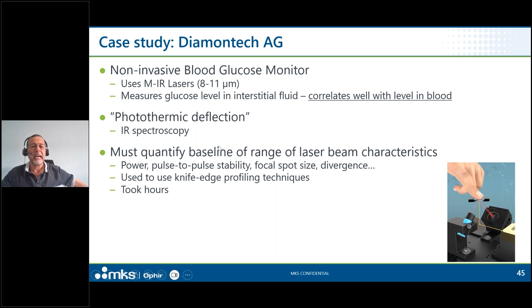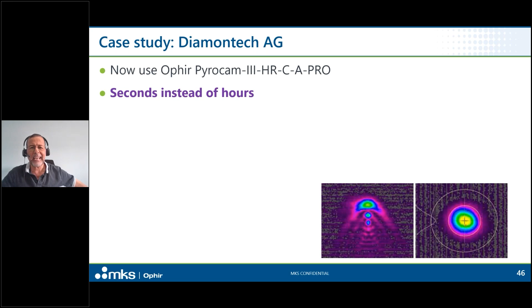So for the beam profiling aspects of this, they used to use classical knife edge profiling techniques in the R&D stage. That, okay, that's fine, but it takes hours to properly do one of those. Now they use an Ophir instrument called the pyrocam. Here's a rendition that they have, I think, from their website of what it looks like. The pyrocam is a beam profiling camera where the imager is an array of pyroelectric detectors, pyroelectric pixels. And now, instead of taking hours to do a profile, it takes seconds.